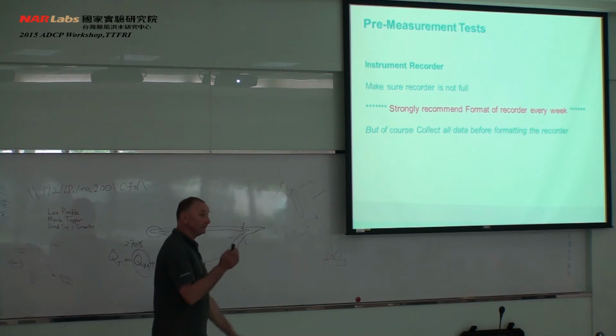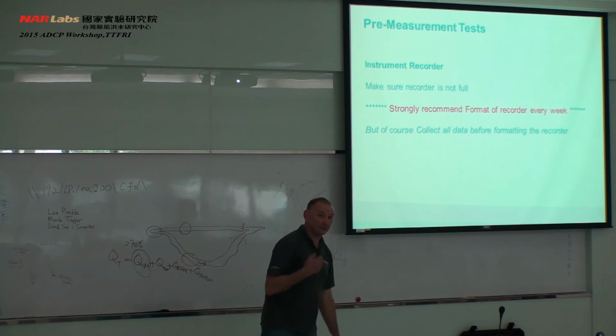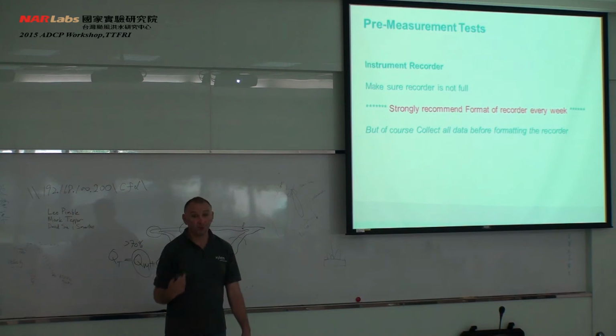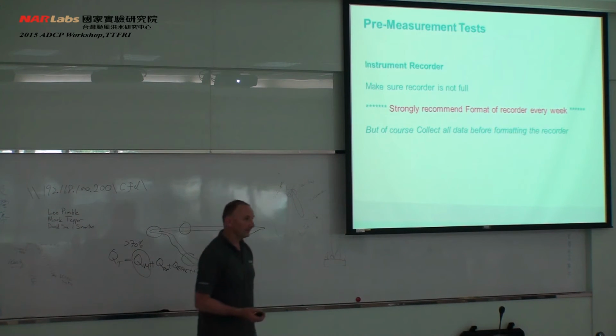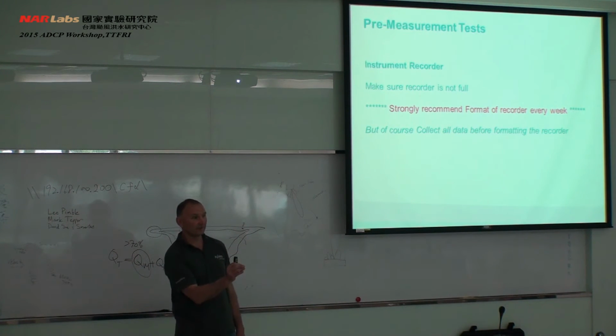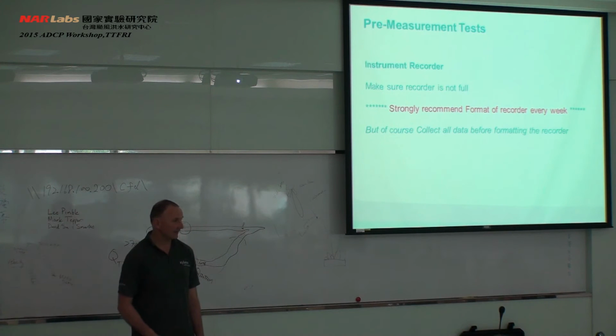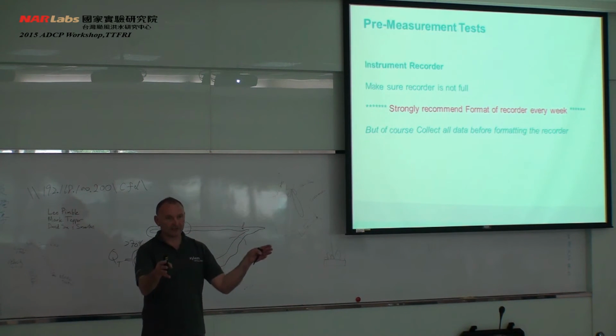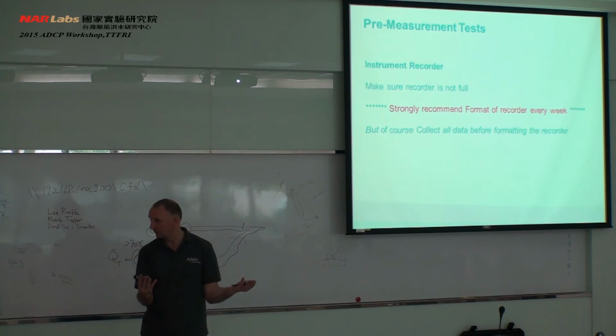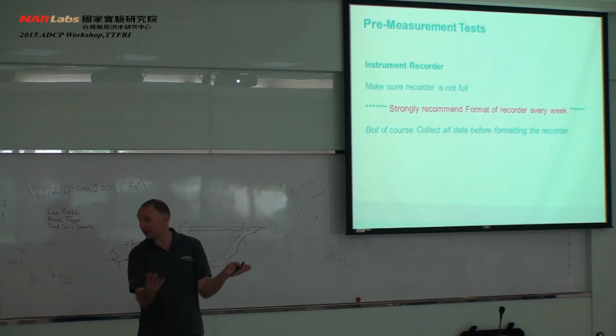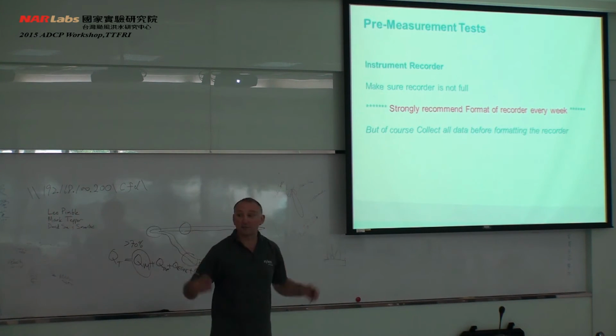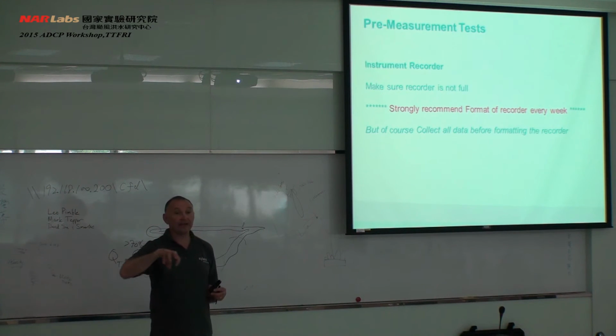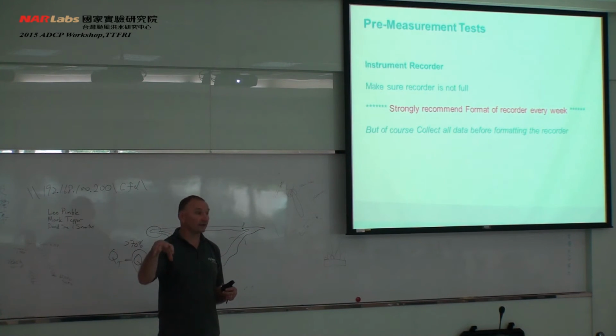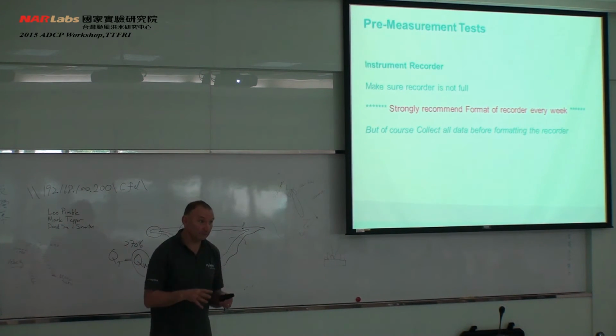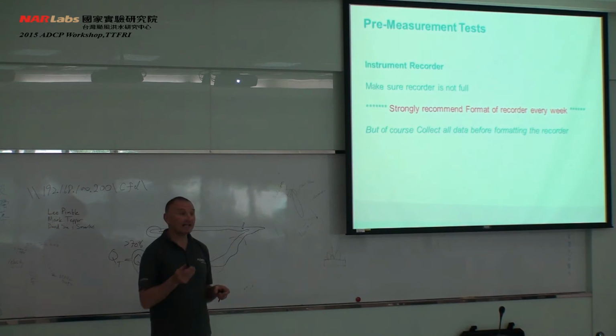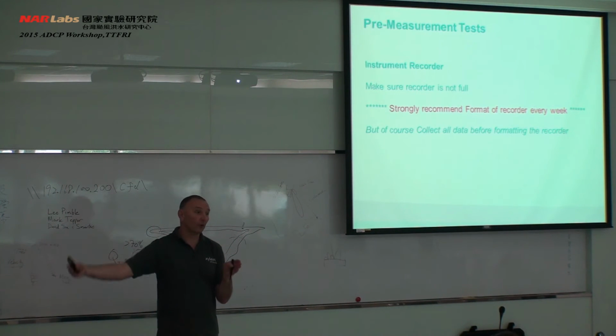We do strongly recommend, and I personally always do it on a monthly basis, that you format the recorder on the instrument. Every time it's collecting data files, we have an 8 gigabyte recorder inside the instrument. When you look at the files, you might have 500 megabyte files, a couple of 500 kilobyte files, a couple of megabytes, whatever. Those are the typical sizes. You might think, oh, 8 gigabytes will go on forever. But actually the instrument is also collecting an awful lot of diagnostic data in the background. Those diagnostic data are an order of magnitude greater in size than the data files that you will be using, and they are filling up the recorder.